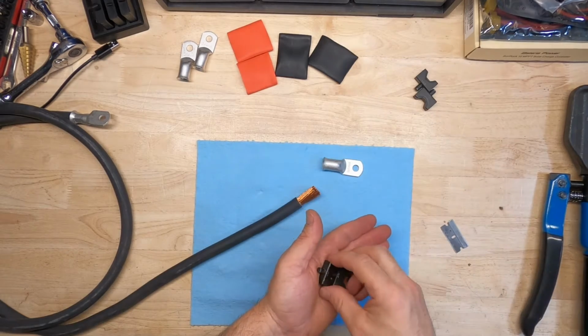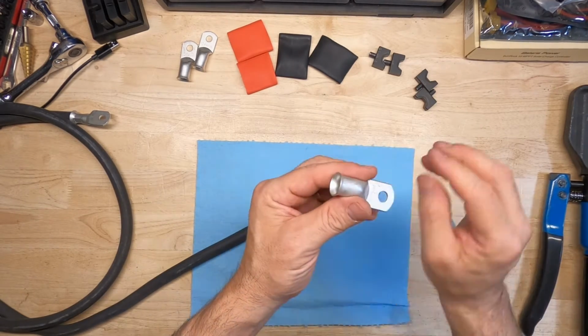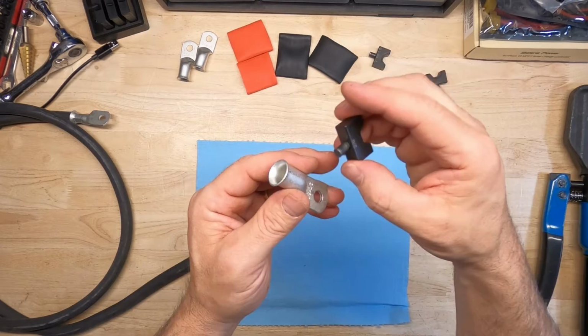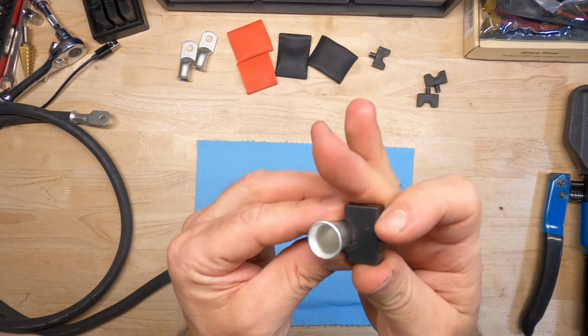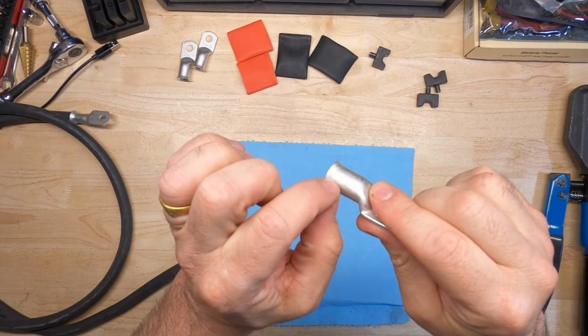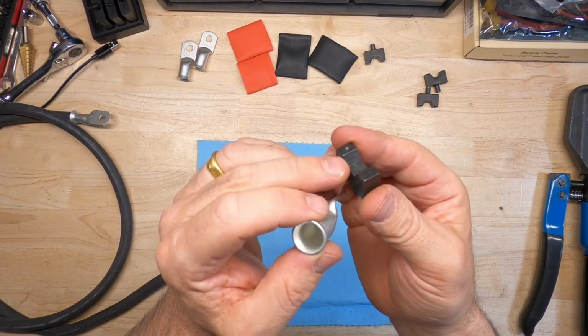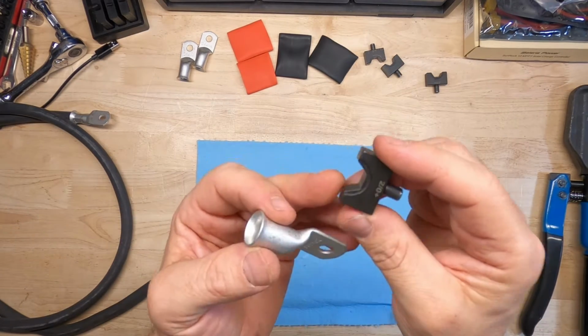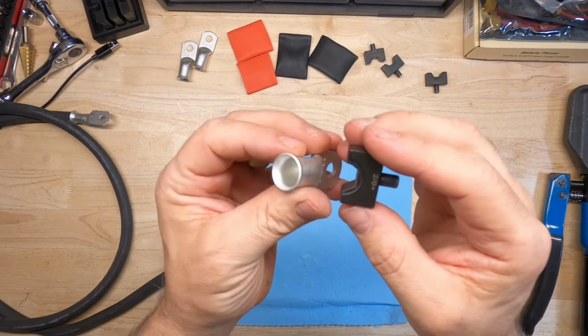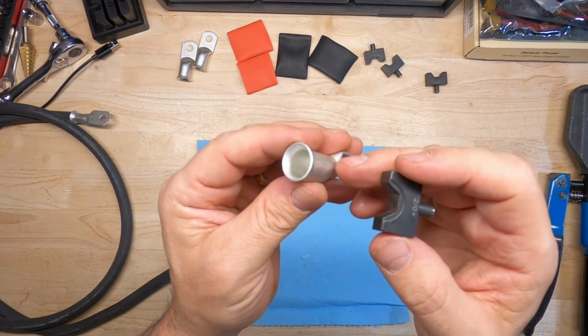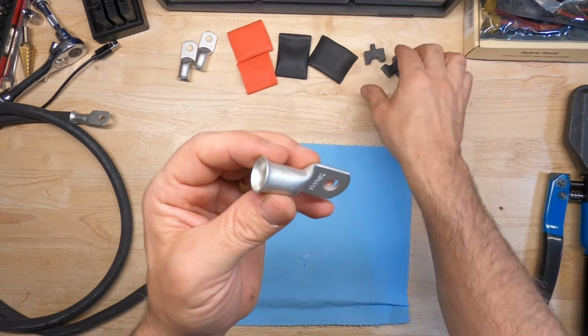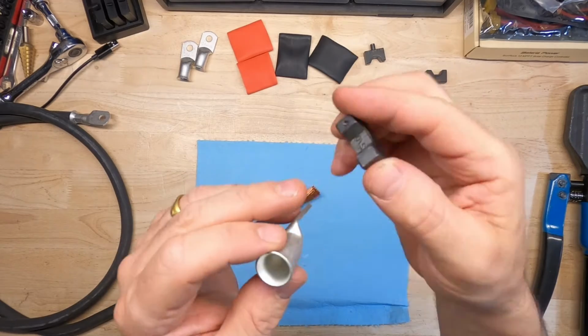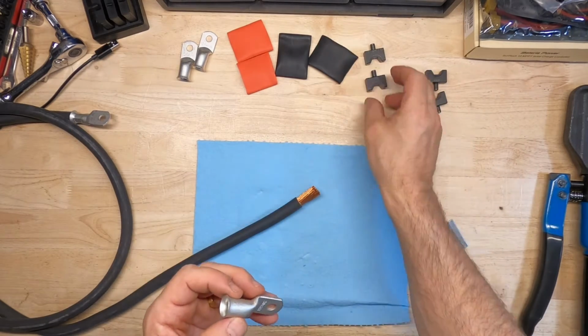So we're going to start with the 2-aught plus, and then we're going to finish with the 2-aught. The reason we do that with these lugs, if I were to start in with the 2-aught and crimp it down, you're going to end up with a little burr. It ends up kind of bleeding out the sides here. If you start with a larger size, it won't be as tight, but you won't have the burrs. But once it's compressed a little bit, then you can go down to your actual 2-aught and finish the crimp.